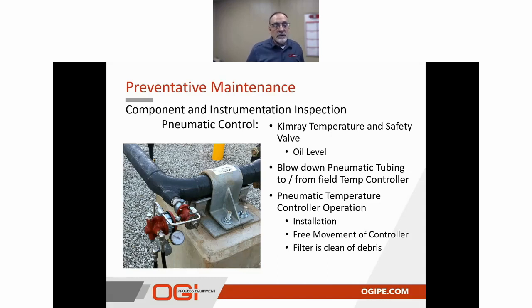And we also want to make sure that the inlet filter is free of any debris. The supply filter is actually just a cartridge that can be removed, cleaned up and blown down. The final thing that we want to look at associated with the pneumatic systems is to ensure that the BASO operation is working properly, actually testing the millivolt signal coming off of that thermocouple going to the BASO, and making sure that it's receiving it and effectively supporting proper operation: in the event that it loses signal, it shuts down, and when there is a flame signal, it operates correctly.